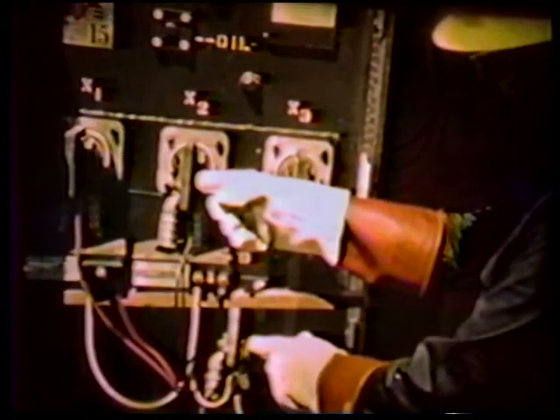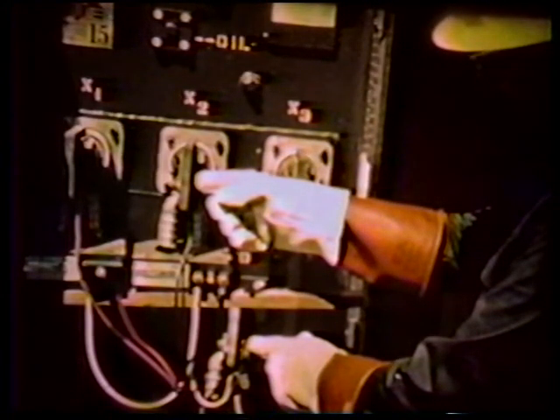For meter installations that require secondary wiring from current transformers or potential transformers, keep in mind that they are located on the incoming service where available fault current is highest. Proper care should be taken when making potential connections. Do not cause phase-to-ground or phase-to-phase faults.